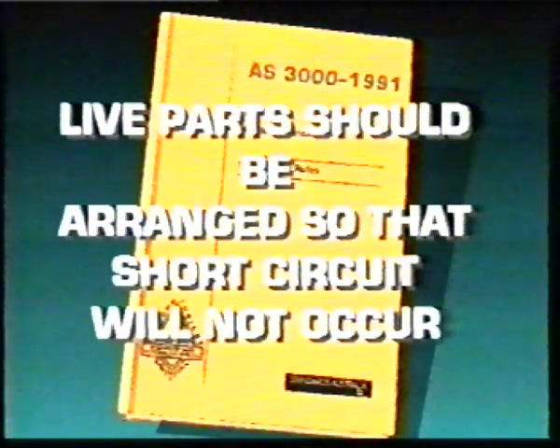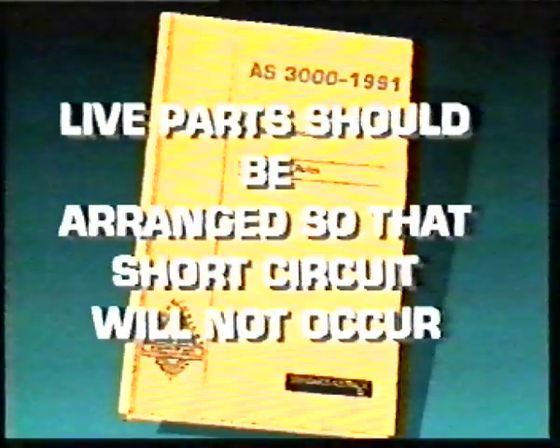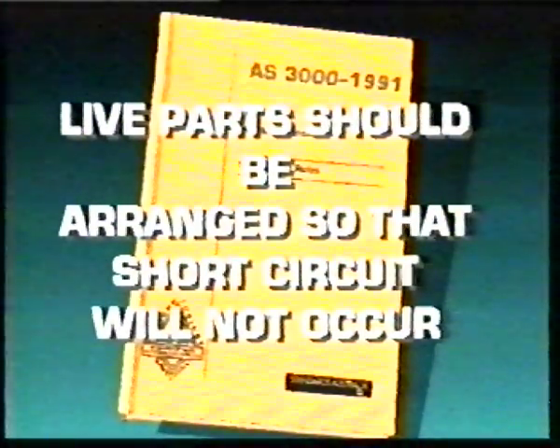This test is necessary because a short circuit current flowing between live conductors can cause considerable damage. This is especially important in high current installations. Here, AS3000 requires live parts to be arranged so that short circuit or arcing will not occur under expected service conditions. Testing should confirm that any resistance measured between the active and neutral conductors of the circuit is consistent with the load. For example, on a socket outlet circuit with no connected equipment, a resistance in excess of 1 megohm should be expected, whereas a 4.8 kilowatt water heater circuit would be expected to have a resistance of 12 ohms.